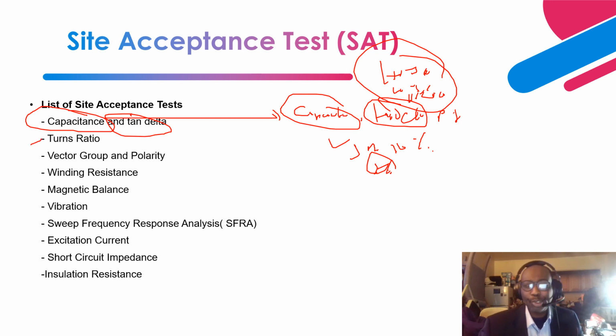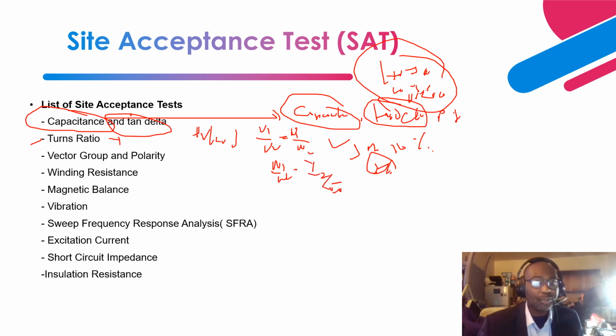Next is the turns ratio. Basically what we are doing is to determine if you have turn shorts, or broken connections of the tap changer. You have any broken strands inside the transformer, right? So what it's doing is taking the high voltage to the low voltage, and that gives you your turns ratio. That is V1 over V2 is equal to N1 over N2, right? And N1 over N2 is equal to I2 over I1, right? That gives you your test ratio.